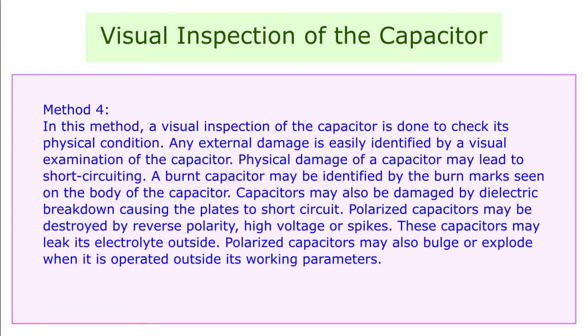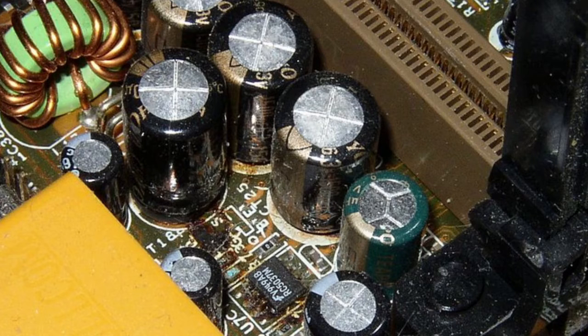Method 4. In this method, a visual examination of the capacitor is done to check its physical condition. Any external damage is easily identified by visual examination of the capacitor. Physical damage of a capacitor may lead to short circuiting. A burned capacitor may be identified by the burn mark seen on the body of the capacitor.